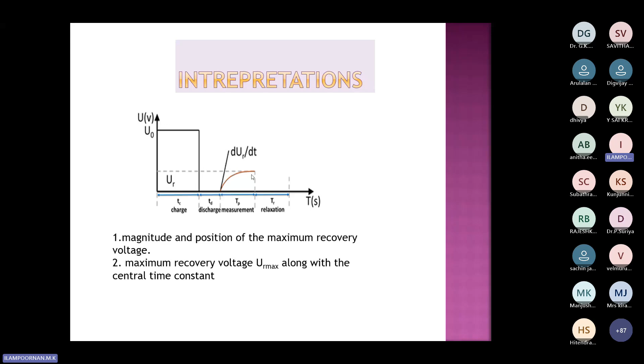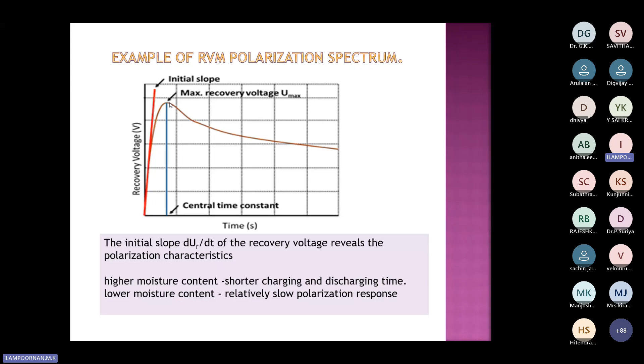I'm just reiterating the point. What we measure in the recovery voltage method is the maximum voltage it can reach, the time taken to reach it - the central time constant - and also the slope, the rate of rise to the recovery voltage maximum. These three components are noted. These are all signatures used to quantify the dielectric strength.